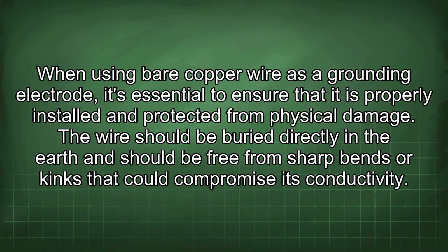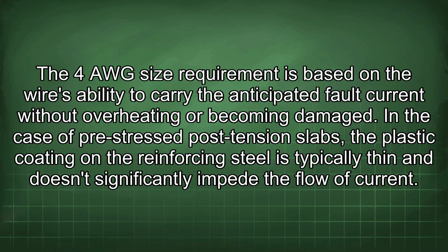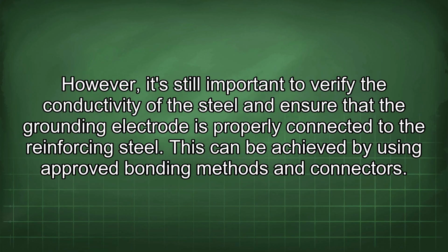When using bare copper wire as a grounding electrode, it's essential to ensure that it is properly installed and protected from physical damage. The wire should be buried directly in the earth and should be free from sharp bends or kinks that could compromise its conductivity. The 4 AWG size requirement is based on the wire's ability to carry the anticipated fault current without overheating or becoming damaged. In the case of pre-stressed post-tension slabs, the plastic coating on the reinforcing steel is typically thin and doesn't significantly impede the flow of current. However, it's still important to verify the conductivity of the steel and ensure that the grounding electrode is properly connected to the reinforcing steel. This can be achieved by using approved bonding methods and connectors.